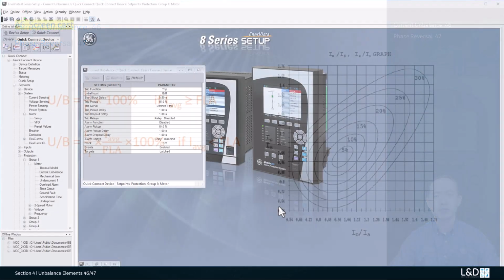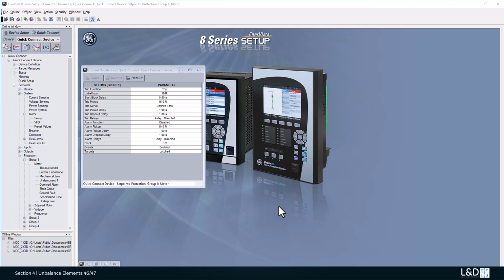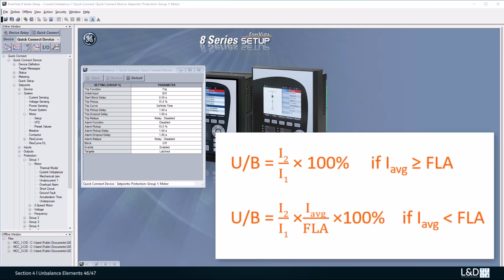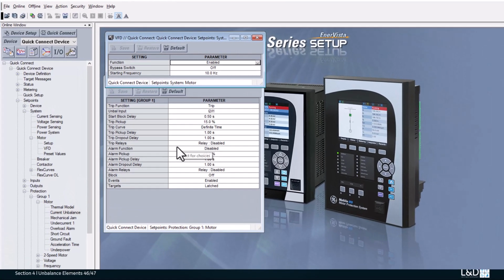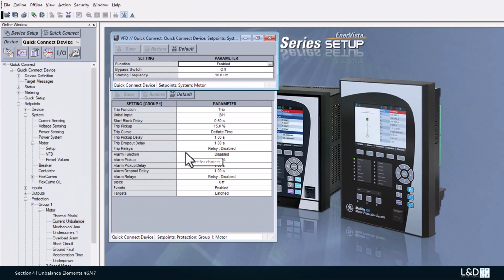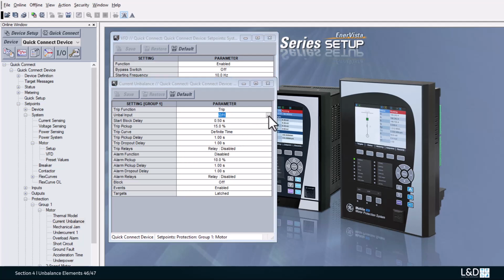In the unbalanced elements, we'll cover the current unbalance 46 and phase reversal 47 elements. Unlike the calculation of the current unbalance in 369, which uses the maximum deviation of current from the average current, divided by the average current or the FLA current, in the 859 relay the unbalance is defined as the ratio of negative sequence current to positive sequence current with an adjustment factor. When the VFD function is enabled, the measurement of the sequence component I2 over I1 from the current phasor may not be accurate, depending on the VFD output currents. Then the lookup table method is used to calculate the unbalanced current value.